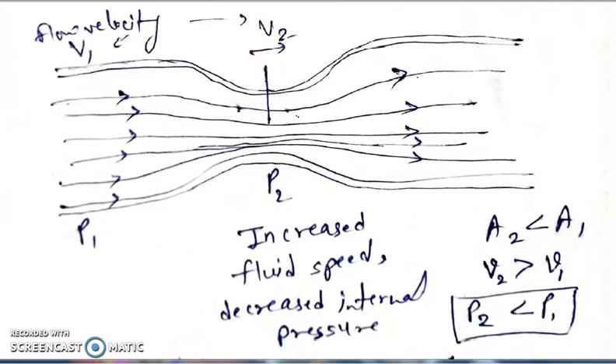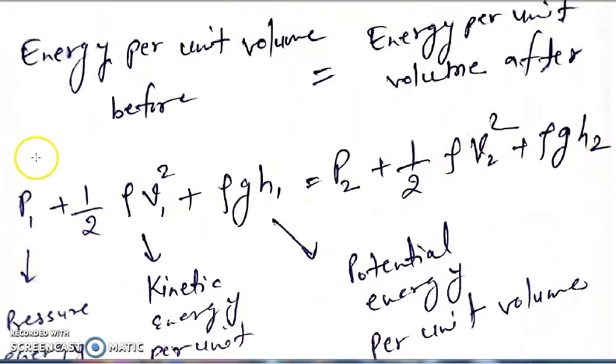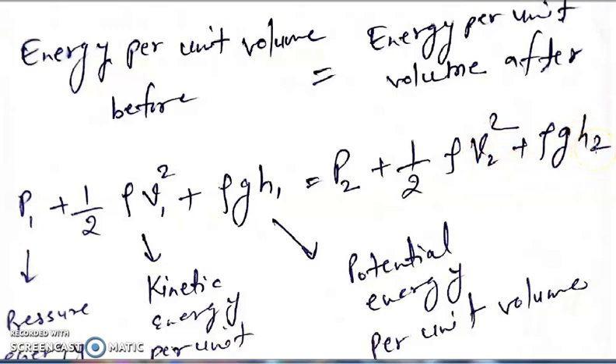When there is an obstruction, the restriction element decreases the area — A2 will be lesser than A1. Due to the decrement of area, the velocity of the fluid increases at the restriction point. So at the restriction point, area decreases while velocity increases. Applying this in the conservation of energy formula — pressure energy plus kinetic energy plus potential energy per unit volume before the restriction equals the values at the restriction. When the new velocity value is applied, the pressure P2 will be decreased.